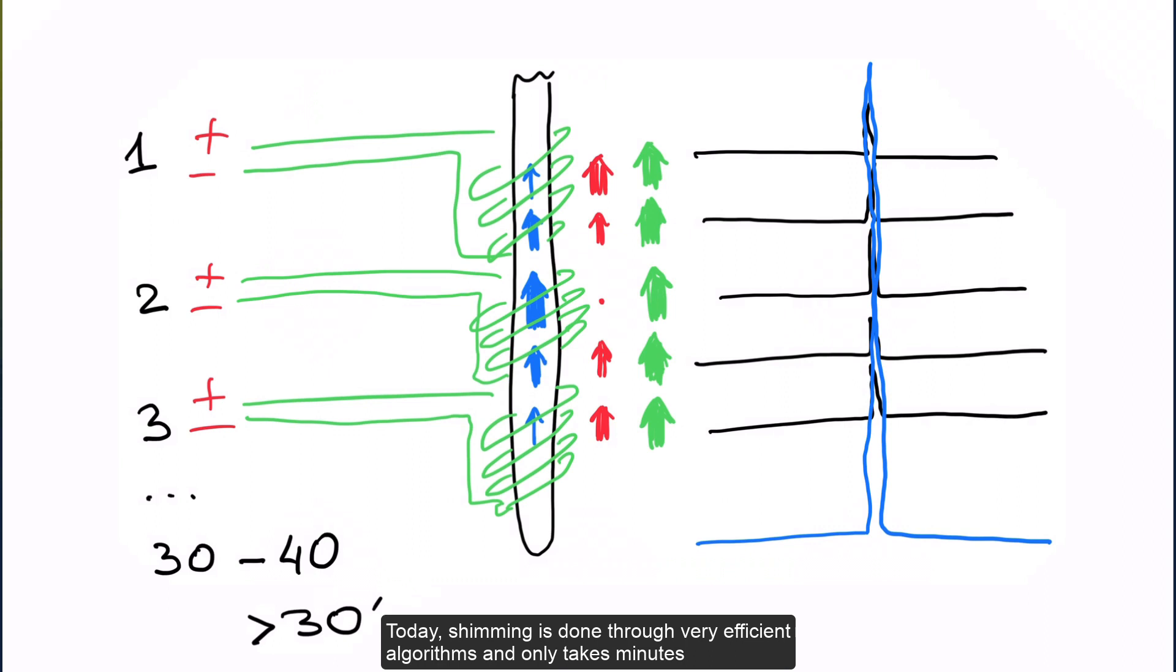Today, shimming is done through very efficient algorithms and only takes minutes. Our job now is to monitor the algorithm performance and direct the shimming process if needed.